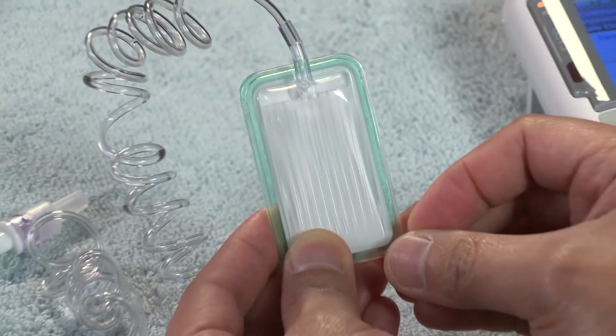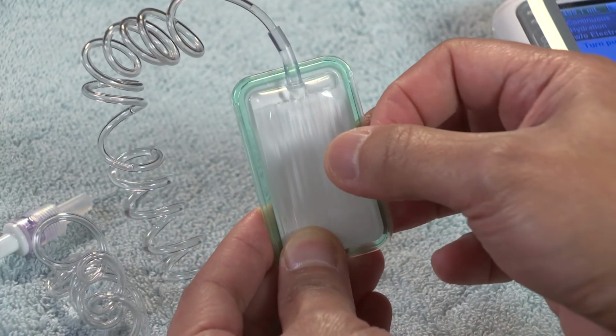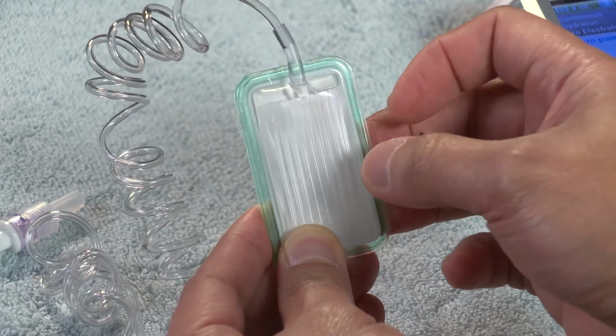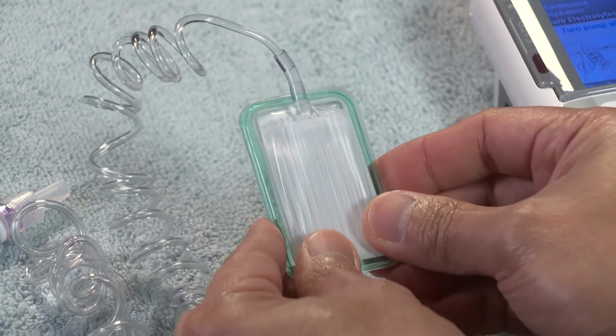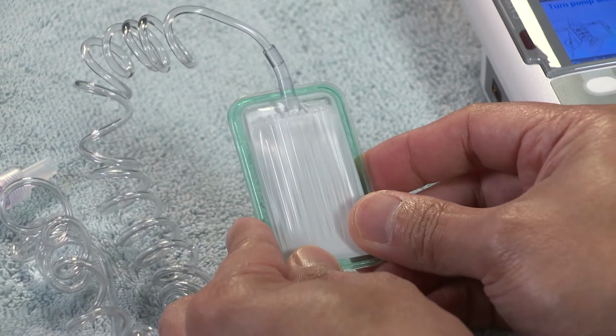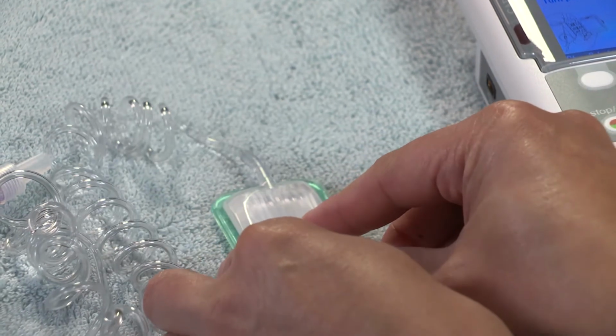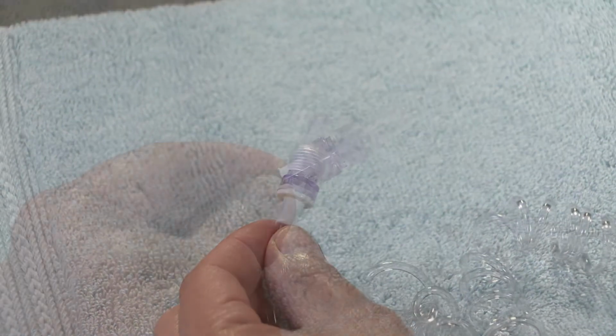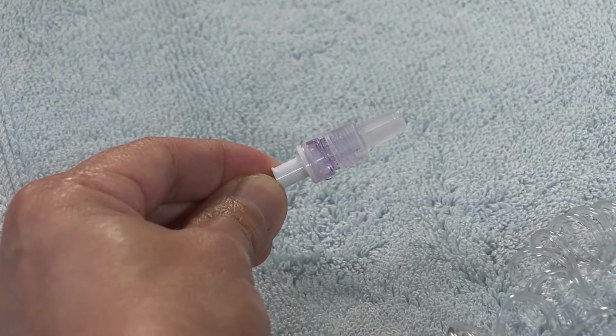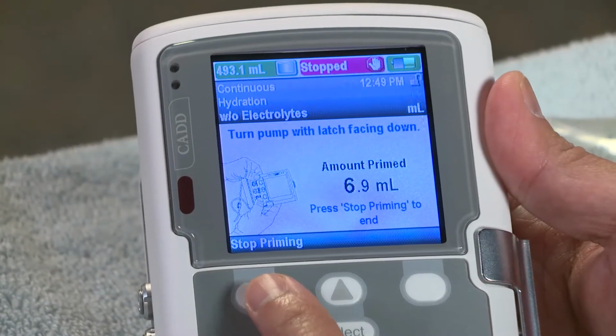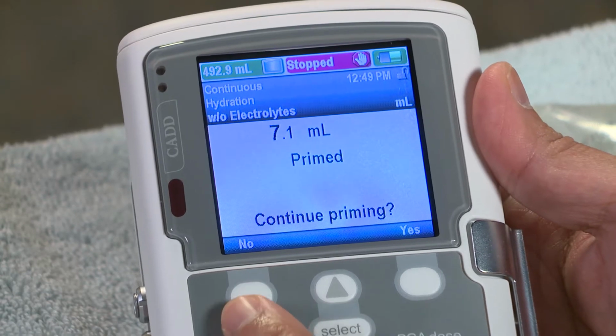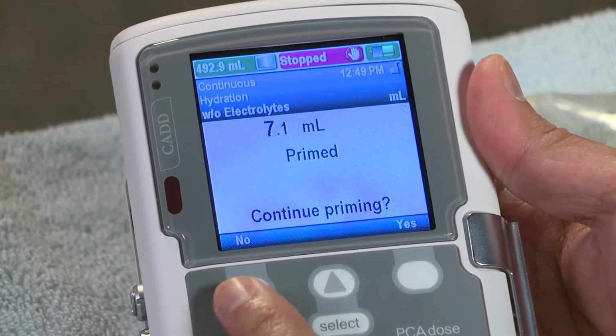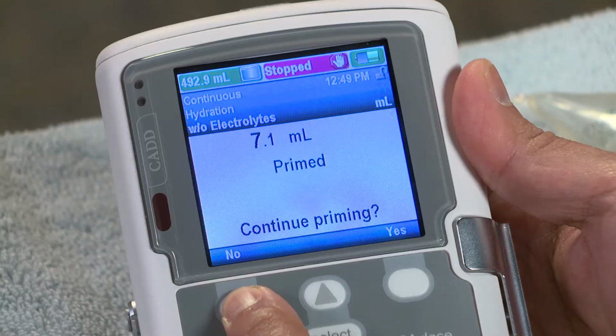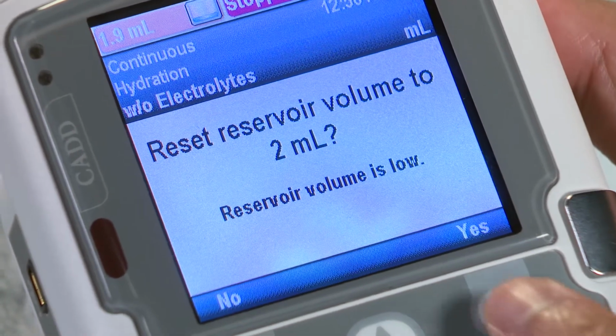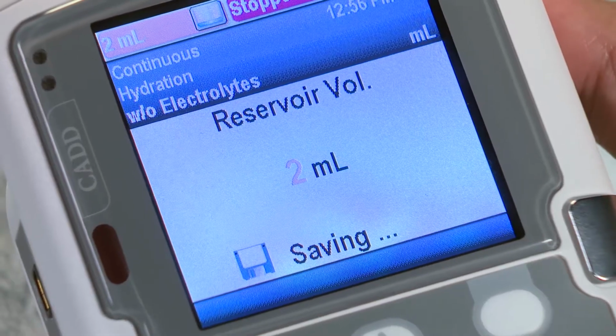Allow fluid to fill the tubing and filter. Watch the ribbed side of the filter, making sure it fills evenly. Tap the filter and tubing as needed to remove any air. The priming process can take a few minutes, so be patient. Allow the fluid to flow until it reaches the end of the tubing. Some drops may come out of the end. This is okay. Press Stop Priming when the fluid reaches the end of the tubing. Press No when the pump displays Continue Priming. Press Yes when asked to reset reservoir volume.